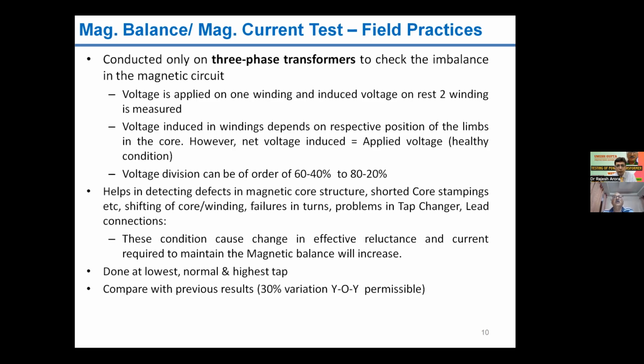However, the total voltage induced in the two windings, if we compare with the winding in which we are injecting the voltage, will be equal to the injection voltage. So the test is performed basically to detect if some issues are there in the core structure, or some shorting has taken place during its operation. Many times this test is also performed if we transport a transformer from one place to another. This also gives some indication about problems in the tap changer and lead connections.